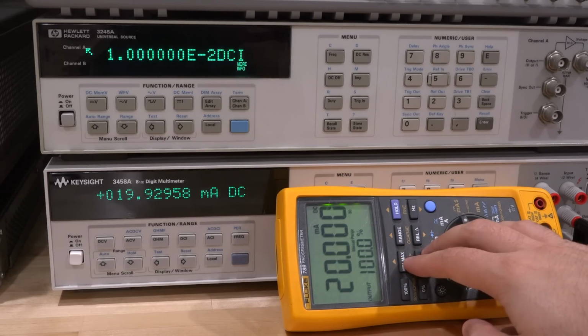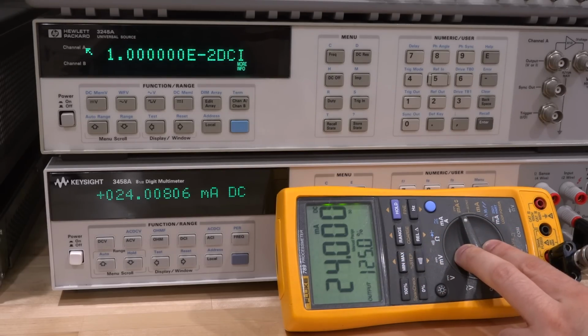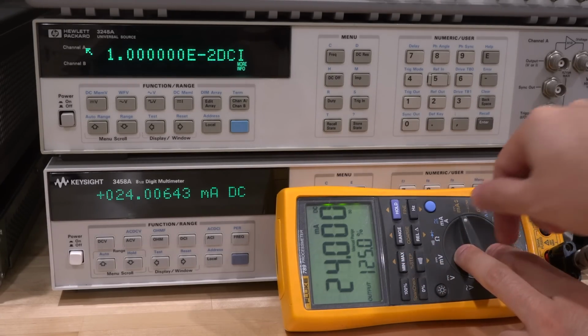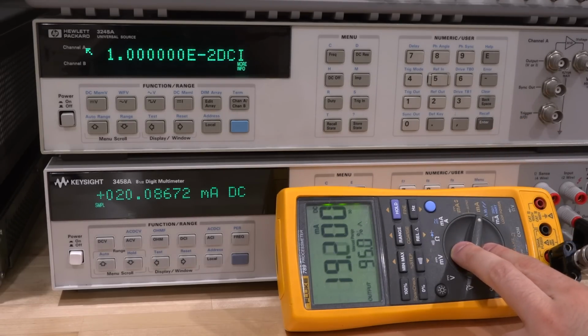And here's 20. And that's pretty good as well. I think the max is 24 milliamp. Yeah, so I think the current source is also working. And on this other point over here, you get a whole bunch of different features. Right now it's ramping. So you can see the current slowly ramping up on the display. And this is useful for measuring some of the loops that this is intended for.